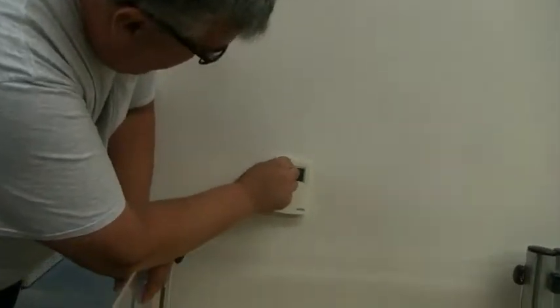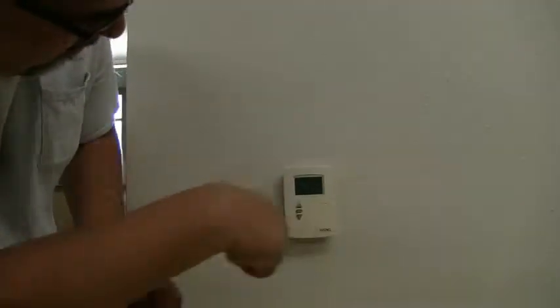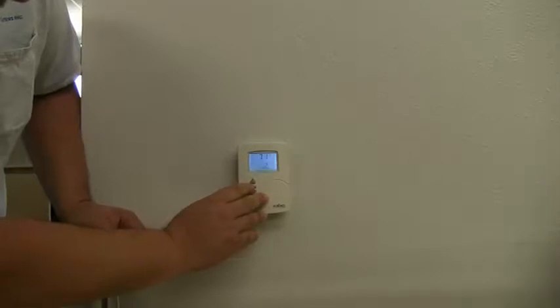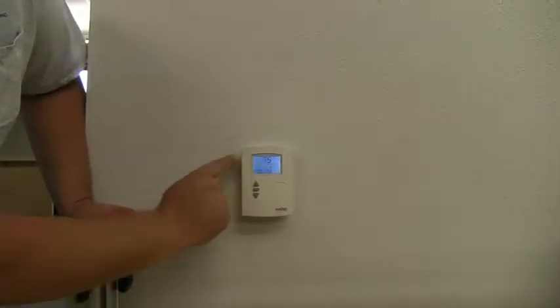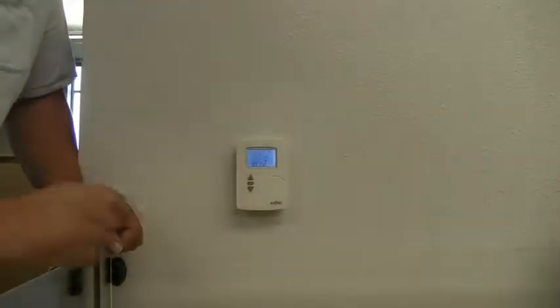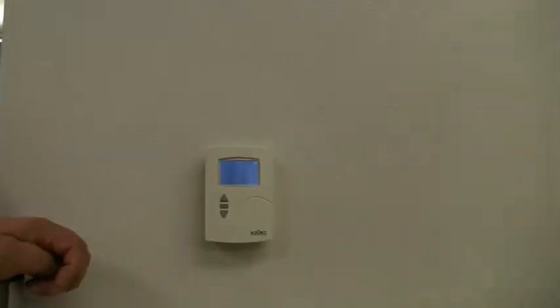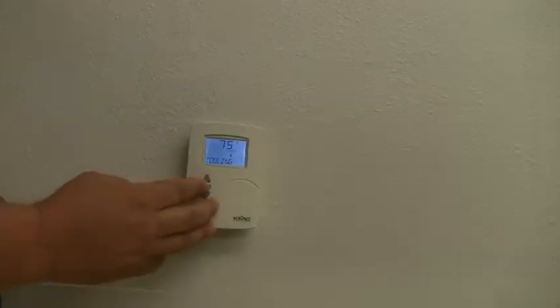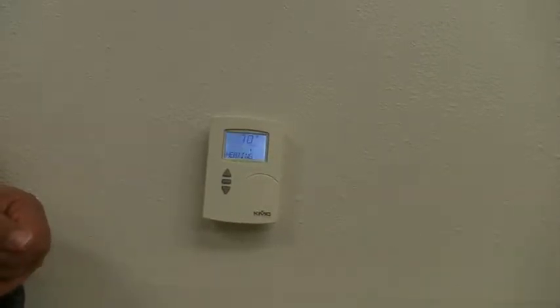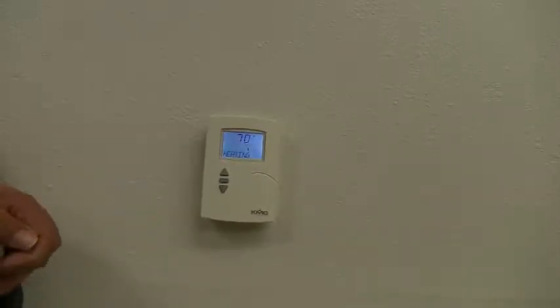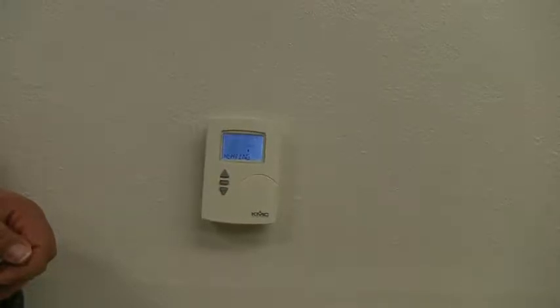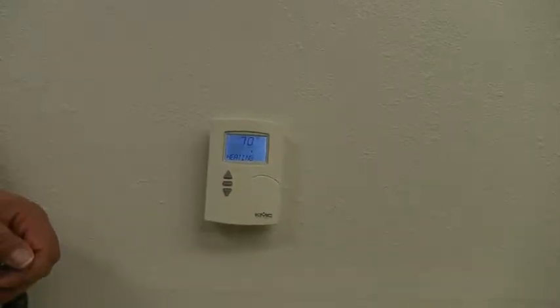And then inside here, I don't know why I didn't take this off. If you hit this button, it lights it up. The first time you hit it, you see it says cooling at the bottom. This is where you adjust your cooling set point. Okay. If you hit it again, it's heating. That's where you adjust your heating set point. Like I said, it's dual set points, so they're separated. You have to adjust both of them separately. You can't adjust one and expect the other to follow. It'll trail by 5, but that's all it's going to do.